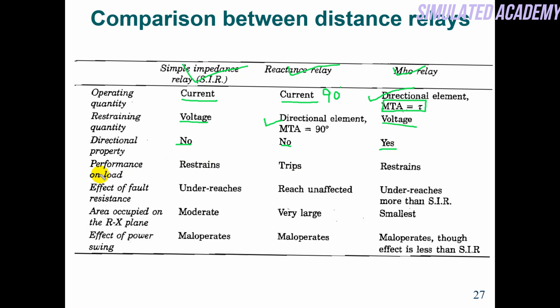Performance on normal load: the Mho relay and simple impedance relay restrain on normal load, whereas the reactance relay trips, which is why we cannot use the reactance relay for transmission protection — a supervisory relay is compulsory for it. Effect of fault resistance: the simple impedance relay under-reaches, the reactance relay does not under-reach because X is not involved, and the Mho relay under-reaches more than the simple impedance relay because the circle is very small.